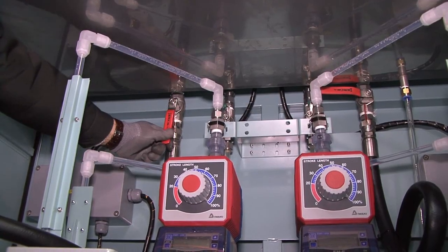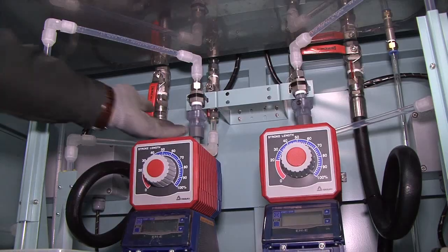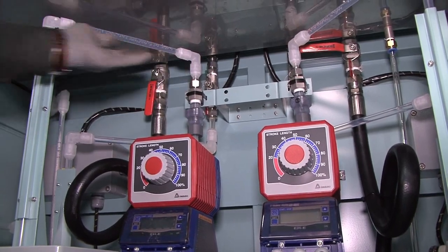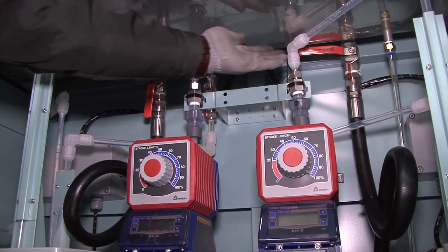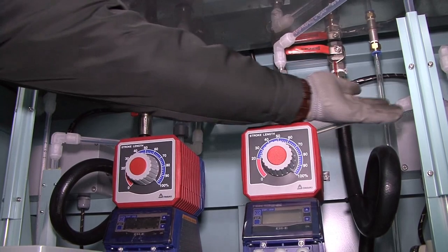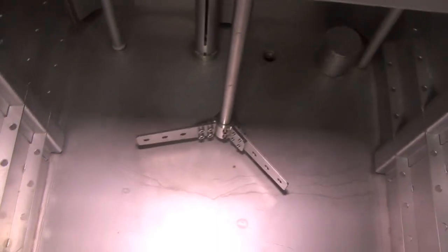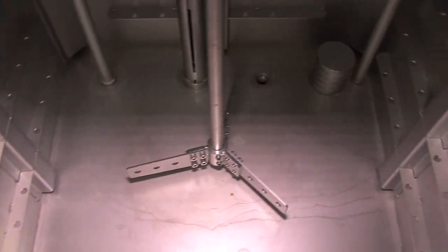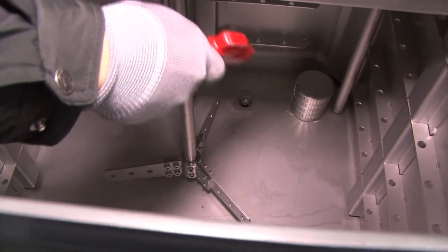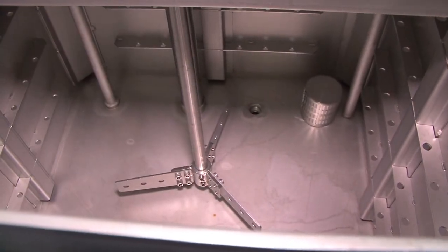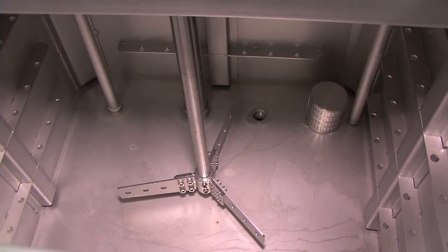Step 3. Turn the draining rubber hose at the bottom of ANU facing outward. Open drain valve, right and left side of the tank at the bottom, to drain neutralizing solution from the tank. Use air to clean up ANU strainer. Step 4. Reassemble the front cover and the side cover of ANU.